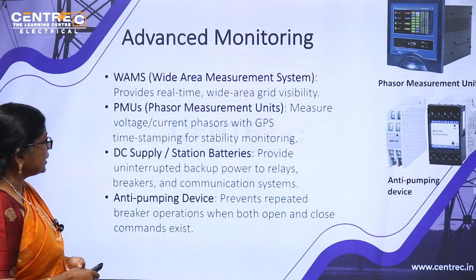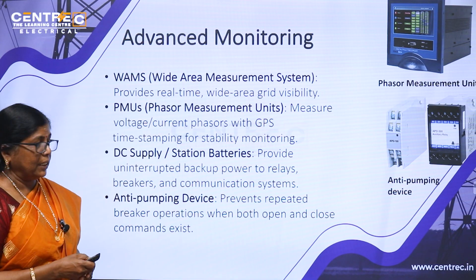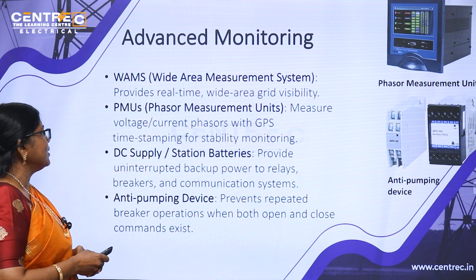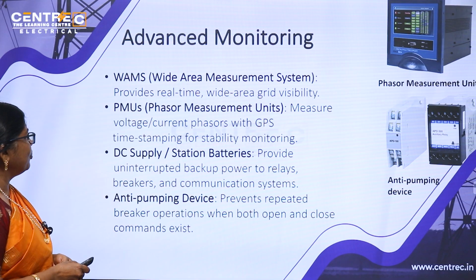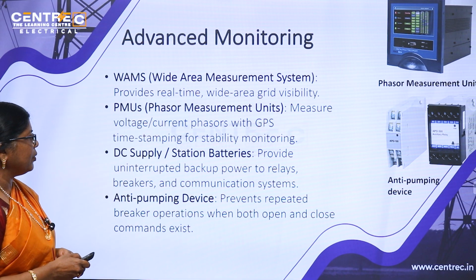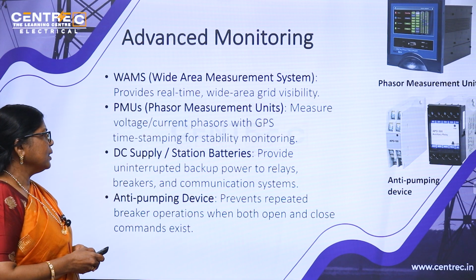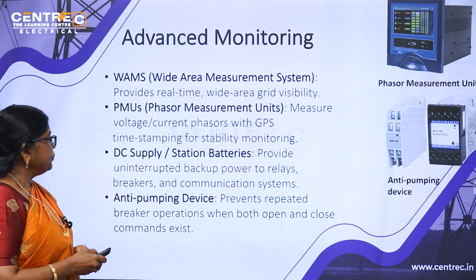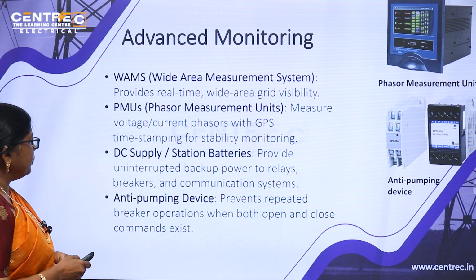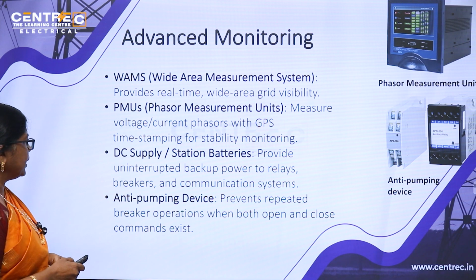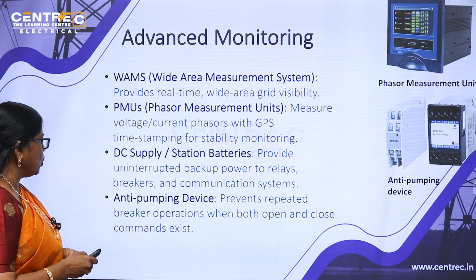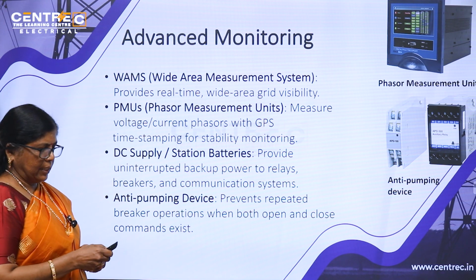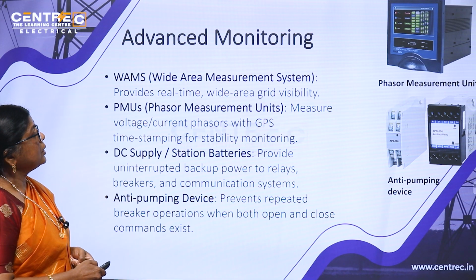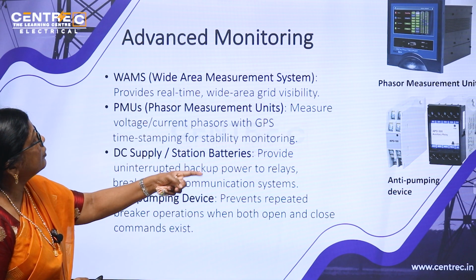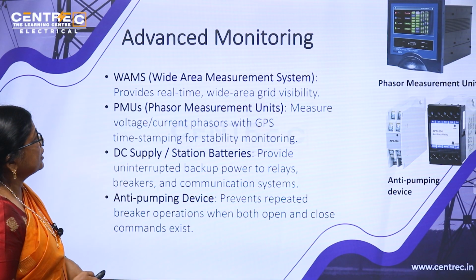DC supply or station batteries, that is an important thing. That is the heart of the station, the DC supply. It provides uninterrupted backup power to relays, breakers and communication system. Anti-pumping devices prevent repeated breaker operations when both open and close commands exist. Reclosing. This is an anti-pumping device. This is a phasor measurement unit.